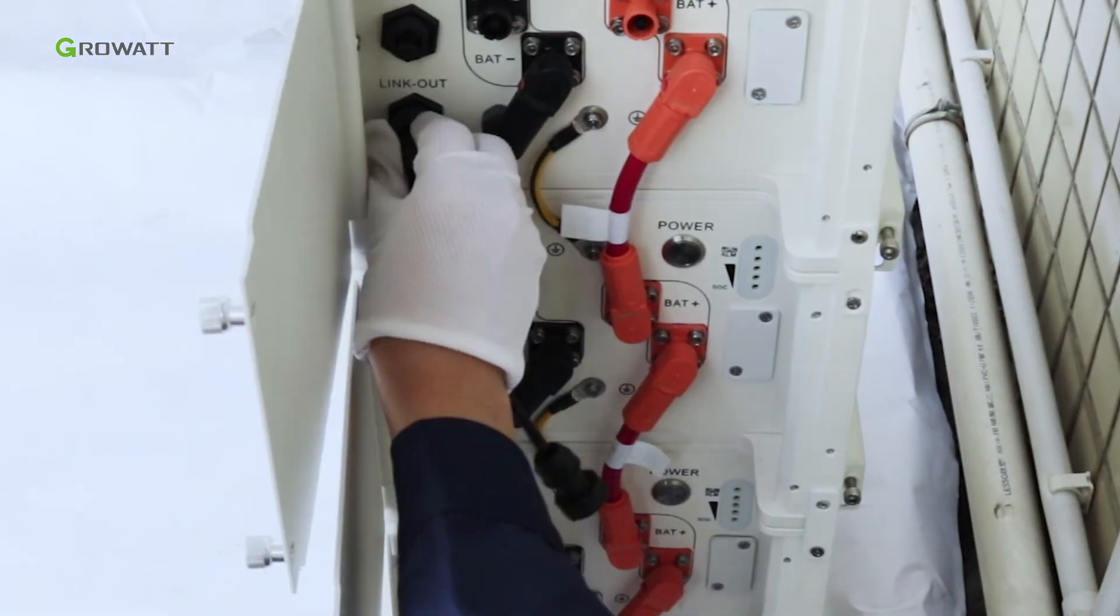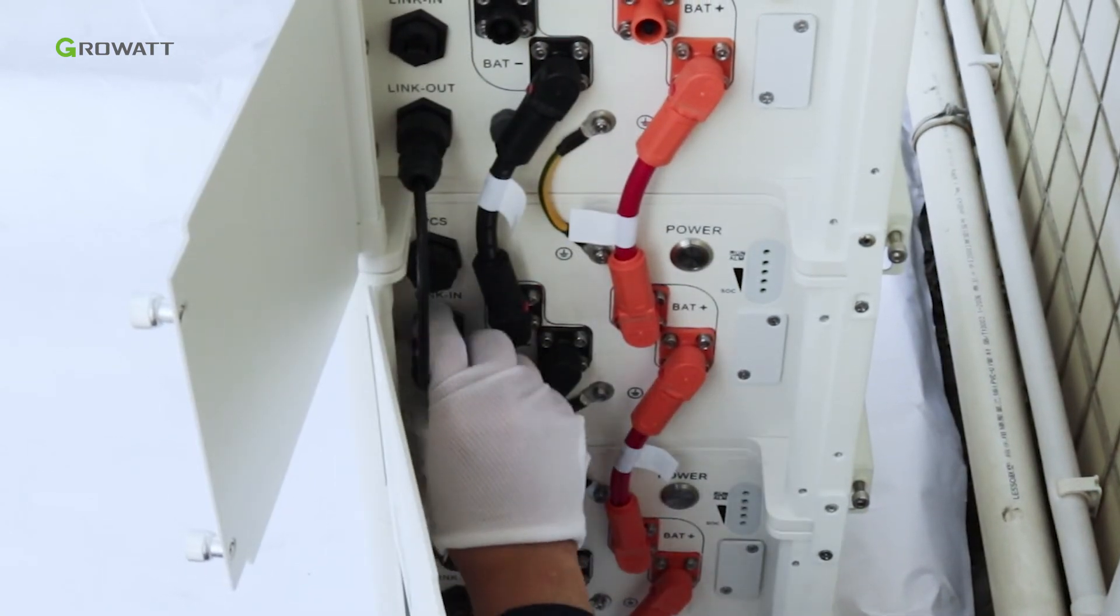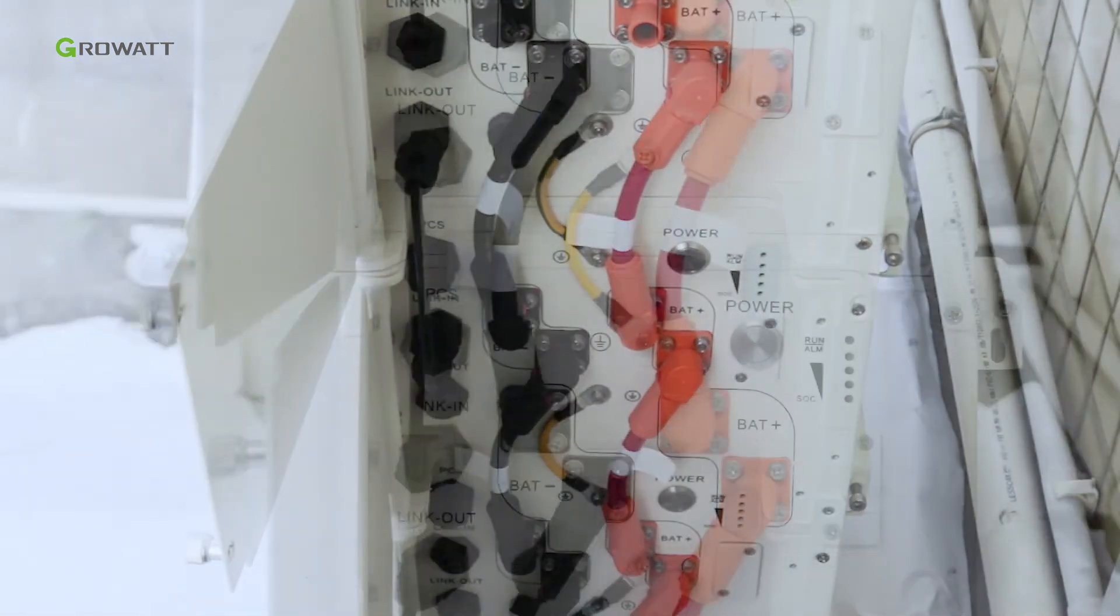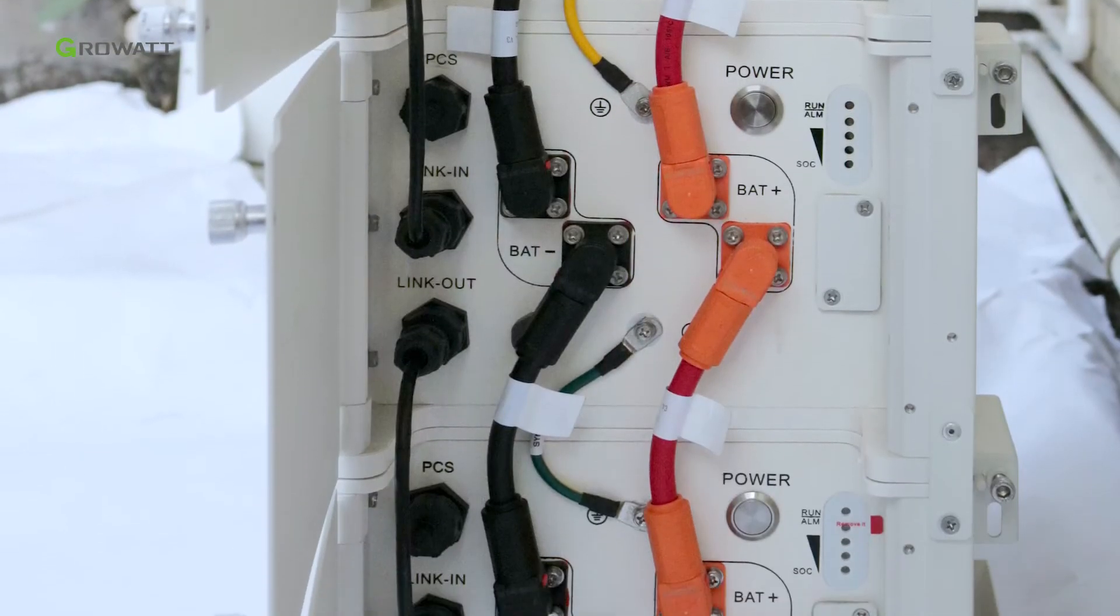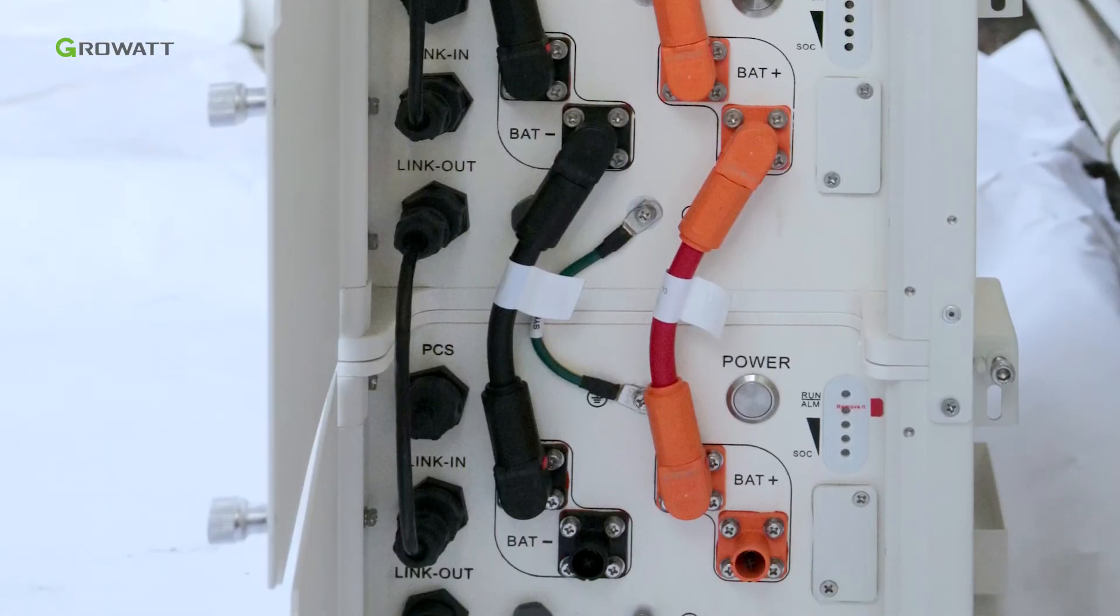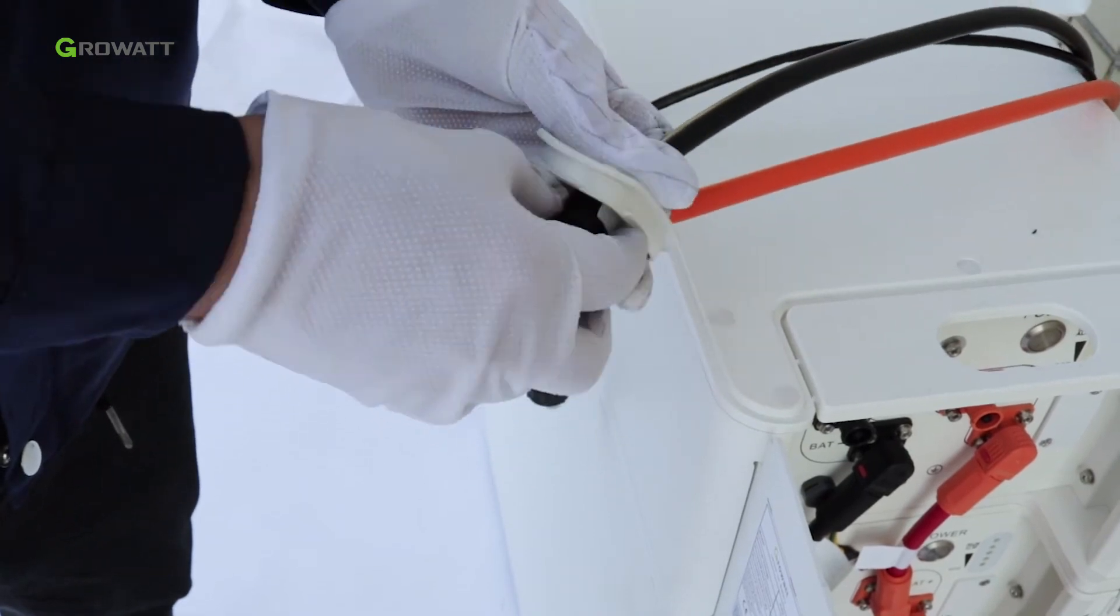Connect the communication cable from the link out port of the top battery pack to the link in port of the next battery pack, and connect all of them one by one. Power and communication cables from the hybrid inverter need to go through the rubber cover.